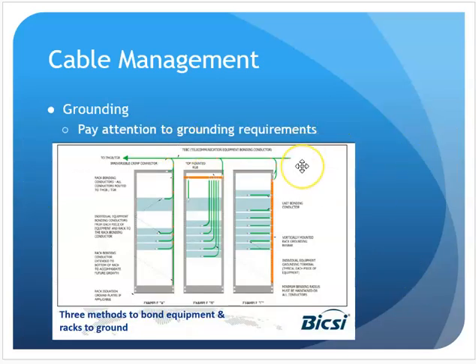As I'm hooking up my equipment racks, I do need to worry about grounding them. So if I have an electrical short, it's not going to energize the rack and all the cable support in hallways. So there are actually grounding wires that need to be attached to them and attached to building ground.